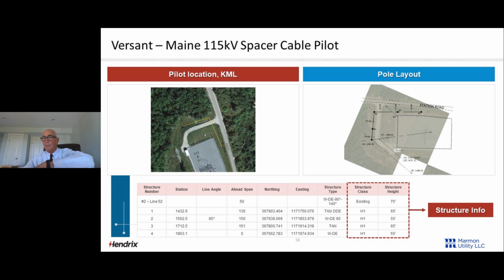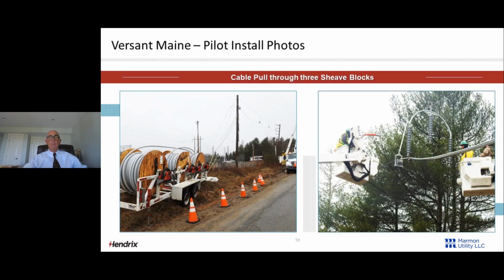Here's the pilot we built in the state of Maine, Versant. It's up by the border with Canada. 5 poles, 4 spans, a couple of dead ends, a double dead end angle, a light angle, and a tangent. During construction, we basically use our normal method with a lot of modifications. Our service experts will be on hand when we install a 115 kV line or 69 kV line at your utility. So we'll be able to figure this out before we do it.